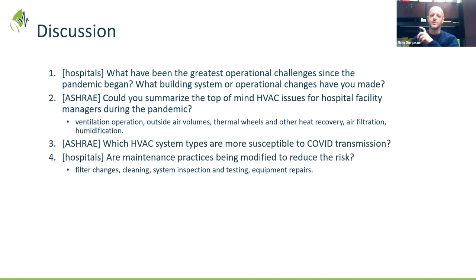Back to your original question about fresh air volumes: it's in our procedure, if we ever have to activate one of those temporary units I mentioned, to crank up the fresh air to 100%. The only thing we've done right now is, we have an on-site dental clinic that can lead to aerosolization of particulates, so we've been proactive in ramping that fan up to 100% fresh air in, 100% exhaust out, and cranking the VAV boxes serving those areas to 100%, 24/7, to help maximize the patients they can see now that they're open again.